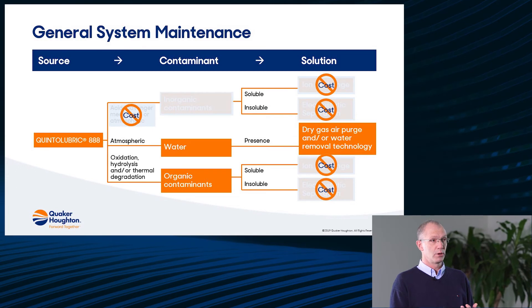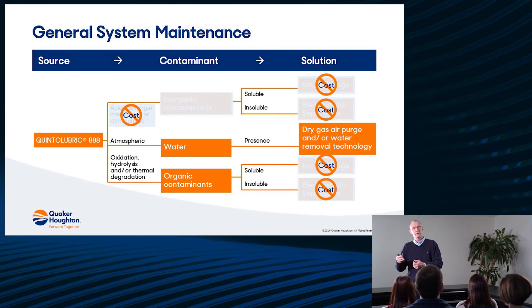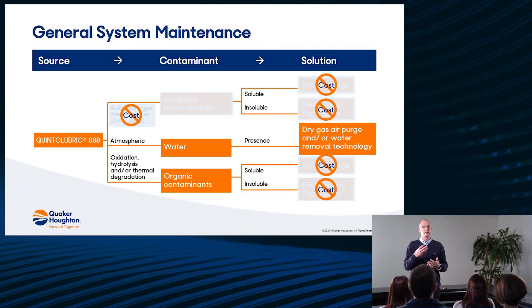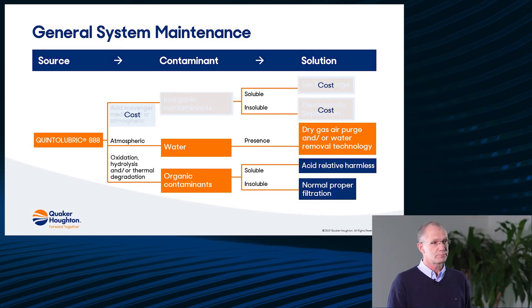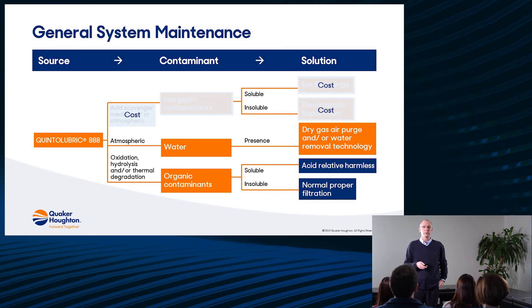If you compare that with polyol ester or QUINTOLUBRIC® 888, the organic contaminants are harmless because they're not so aggressive, so you don't need ion exchange systems or special filtration systems — saving a lot of money. And if you don't have to use the acid scavenger system, the chance of inorganic contaminants is much lower, which means you don't need ion exchange to remove soluble and insoluble contaminants from the fluid. You save money because you don't have to do so much maintenance, as the products formed are relatively harmless.